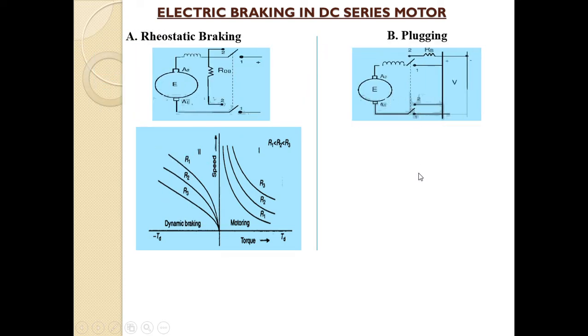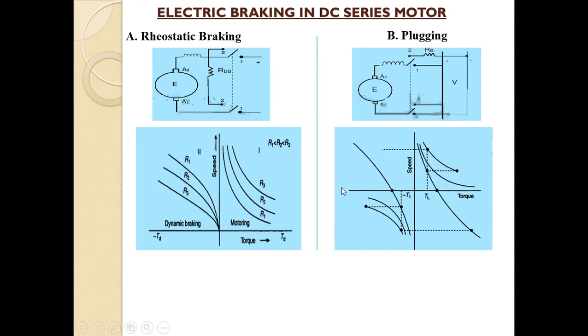For plugging in the DC series motor, we interchange the polarities of the supply. The graph shows all four quadrants of operation. Plugging is involved in either the second or fourth quadrant operation only, but the diagram shows the first and third quadrants as well, because the graph illustrates how torque changes from positive to negative polarity and how speed changes from normal rotation to opposite-side rotation.